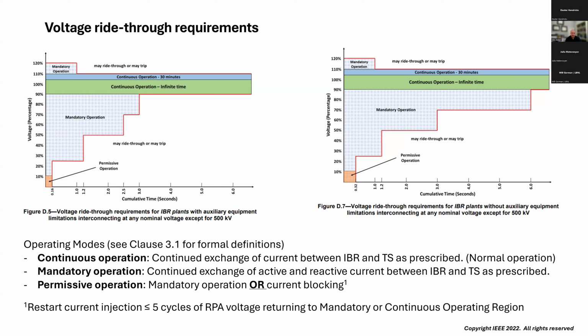Continuous operation, I think of as just the normal mode of operation. There are some exceptions as you get closer to the lower voltage band here, specifically closer to 90%. Maybe you have to pick a priority to maintain both your active and reactive or voltage control objective. But for the most part, that's business as usual, normal operation.